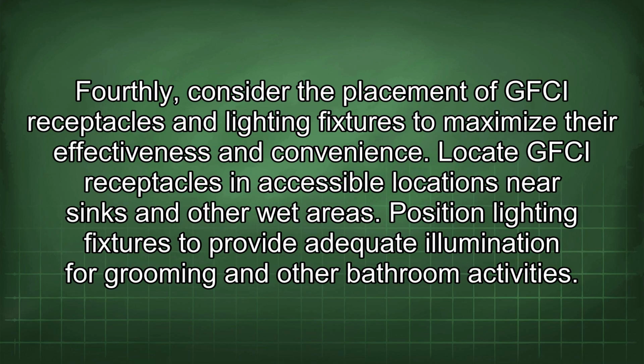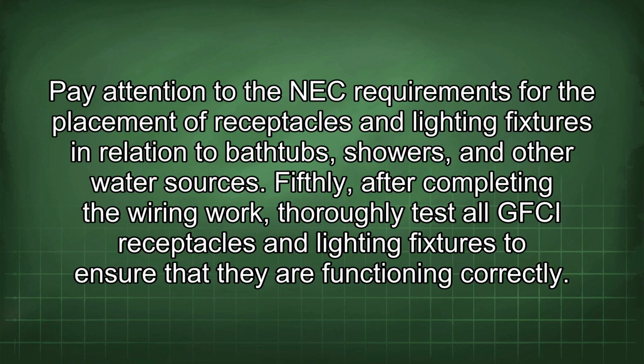Fourthly, consider the placement of GFCI receptacles and lighting fixtures to maximize their effectiveness and convenience. Locate GFCI receptacles in accessible locations near sinks and other wet areas. Position lighting fixtures to provide adequate illumination for grooming and other bathroom activities. Pay attention to the NEC requirements for the placement of receptacles and lighting fixtures in relation to bathtubs, showers, and other water sources.